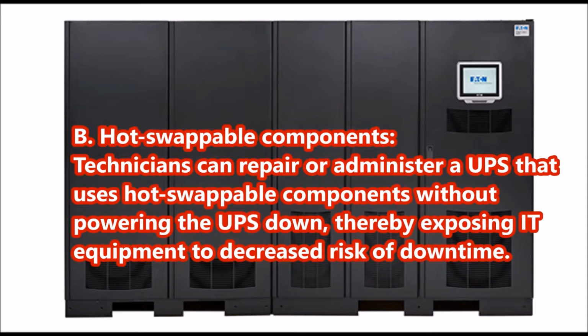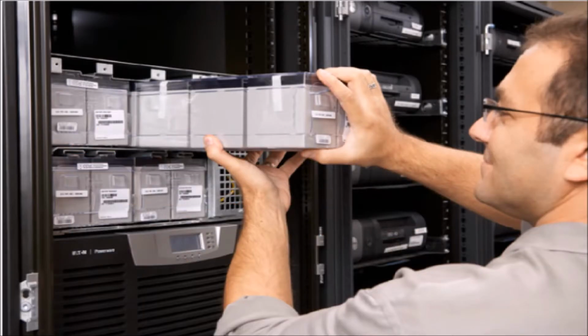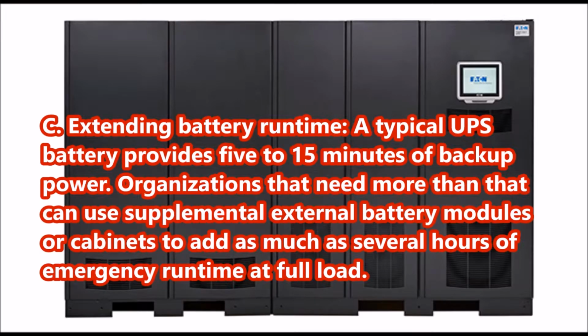Hot swappable components. Technicians can repair or administer a UPS that uses hot swappable components without powering the UPS down, thereby exposing IT equipment to decreased risk of downtime. This picture shows how hot swappable battery modules allow service work to be performed while load equipment remains protected. Extending battery runtime. A typical UPS battery provides 5 to 15 minutes of backup power. Organizations that need more than that can use supplemental external battery modules or cabinets to add as much as several hours of emergency runtime at full load.